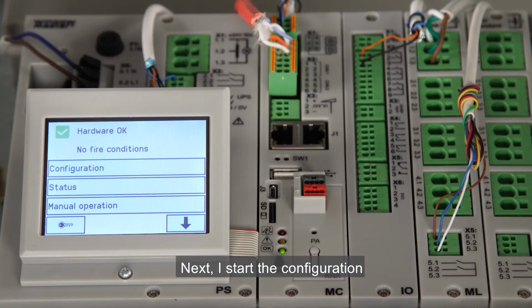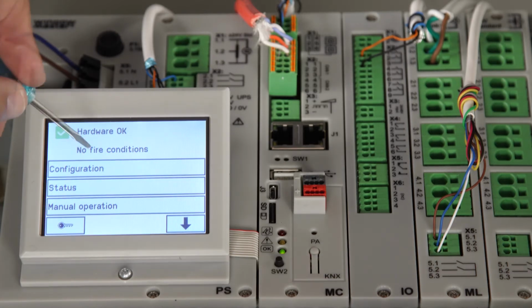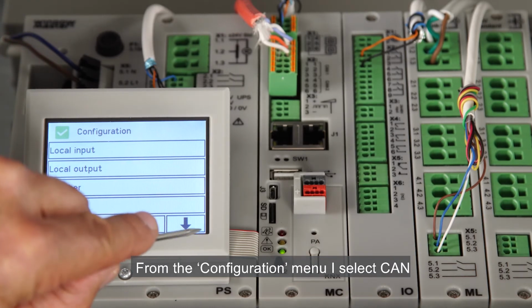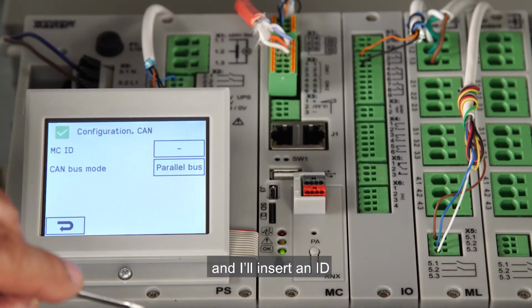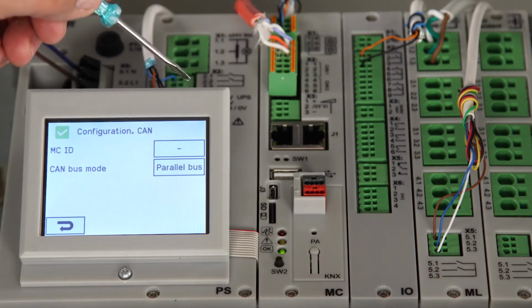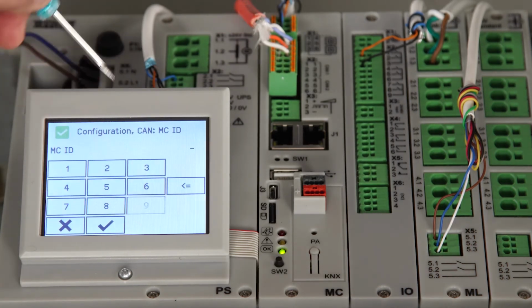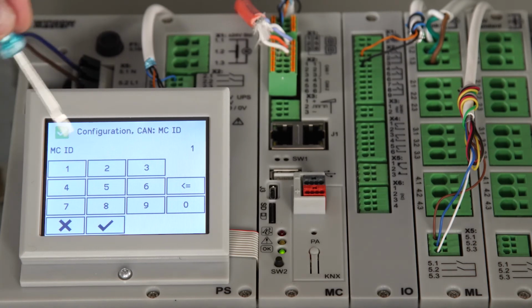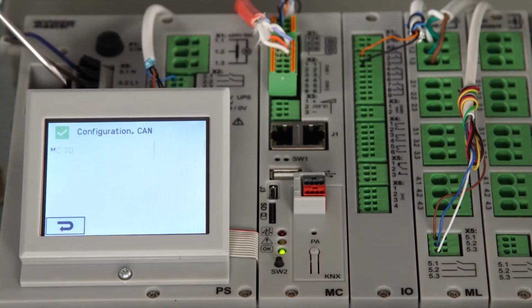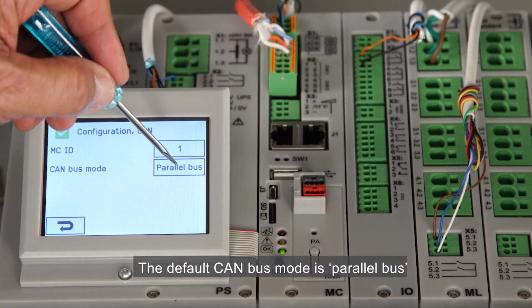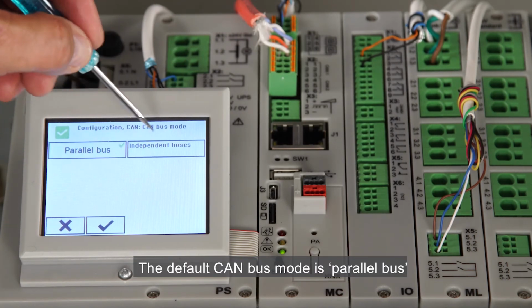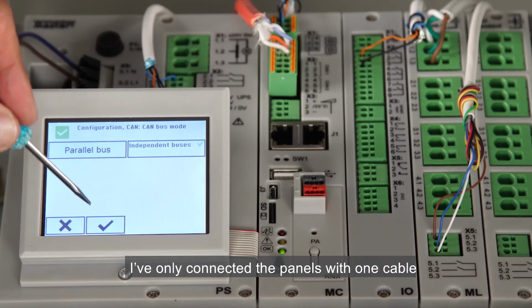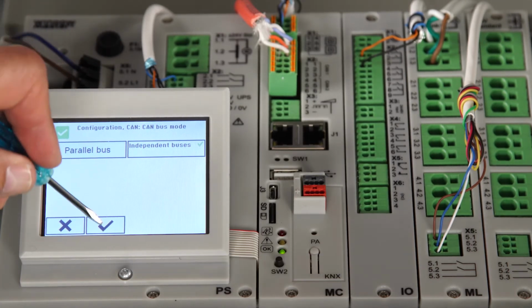Next, I start the configuration. The first thing to do is to assign CAN bus IDs to the panels. I do it first on the master panel. From the configuration menu, I select CAN and I'll insert an ID. I select 1. The default CAN bus mode is parallel bus, which I need to change because I've only connected the panels with one cable.